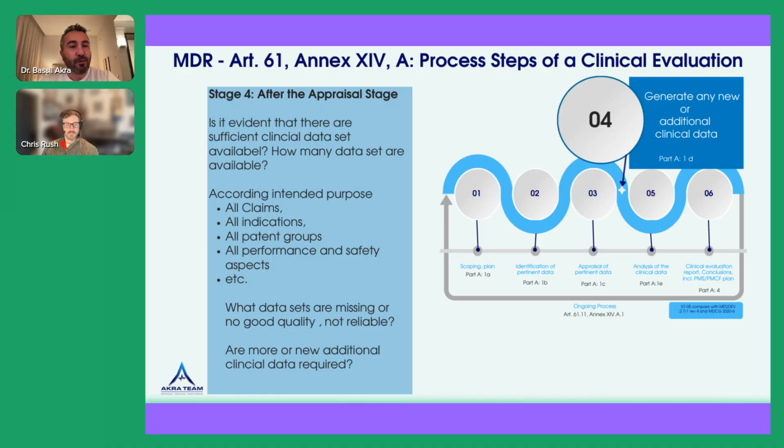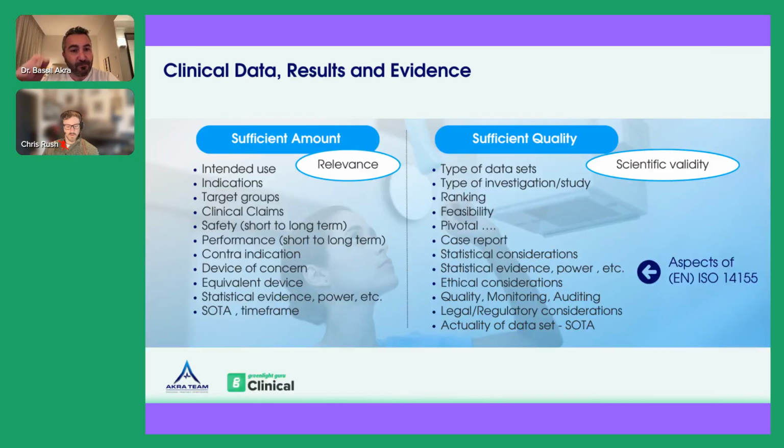But if you have a patient population which is getting 1 million devices per year, you cannot say, I don't have an ability to collect data. But then you need to understand the principle of collecting data, and what kind of data would enable me to move from MDD to MDR, remembering what I told you about supportive devices and devices providing their safety and performance by direct clinical data, where you can study them directly by themselves.